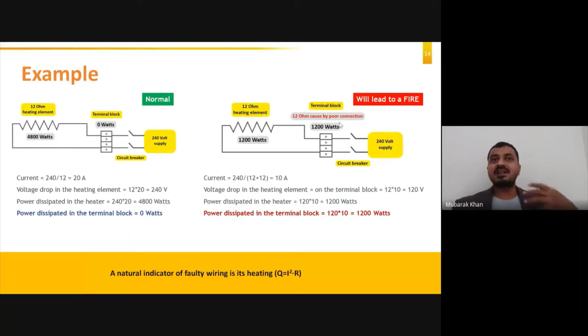Okay. As we saw, the loose connection can cause overheating, as I explained 2 slides back. When there is overheating in a copper bus bar, at high temperatures, the copper reacts with the ambient atmosphere, and a copper oxide film is formed on top of the copper layer. Now, because of this film, the contact resistance increases. So as we saw, loose connection caused overheating, overheating caused oxidation, and oxidation again caused an increase in resistance. This increase in resistance will cause more overheating, which will cause more oxidation, and again more increase in resistance. And it will be a cyclic effect. Because of this, the temperature of the bus bar can increase sufficiently for the bus bar to melt. This is known as the thermal runaway fire hazard in an electrical panel.